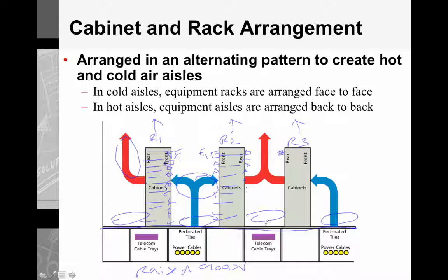So we call this the hot aisle. This is your hot aisle, and that's your cold aisle. That's your cold aisle. So as you can see, we have cold aisle and hot aisle, cold aisle and hot aisle, and so on and so forth. Whenever the rears of the servers look at each other, it's the hot aisle. Whenever the fronts of the servers look at each other, it's the cold aisle.